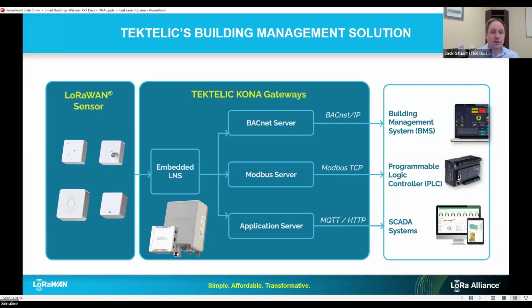As a quick example, let's say you want to add a battery-powered temperature sensor throughout your building for more granular HVAC control. You can deploy the wireless LoRaWAN sensors anywhere in the building, connect them wirelessly via LoRaWAN to the gateway with the embedded network server inside, and then map those data points directly into BACnet objects, such as analog input or binary input. Those data points then appear in your existing building management dashboard, just like any other sensor.